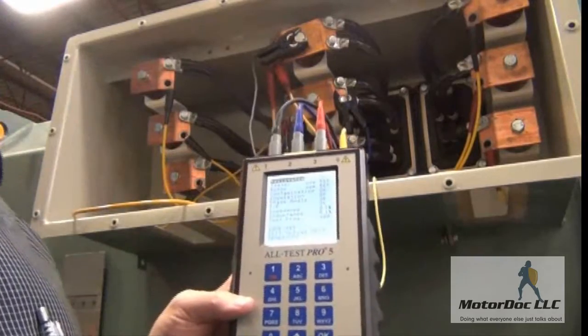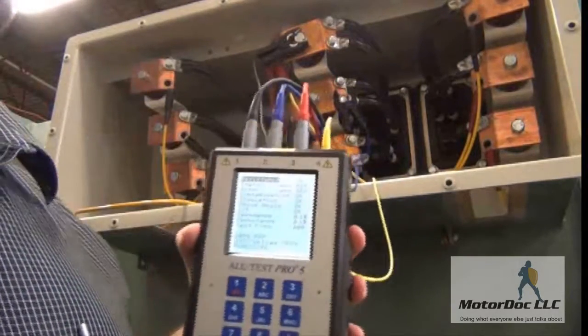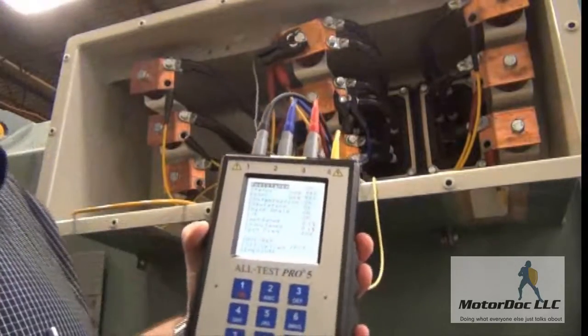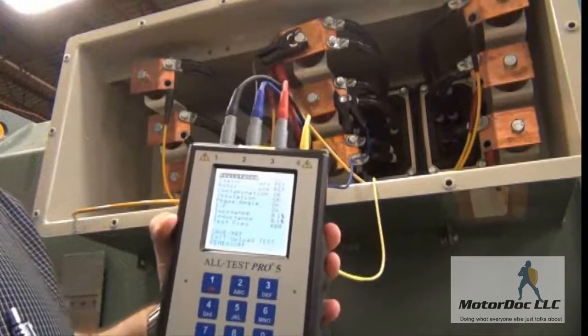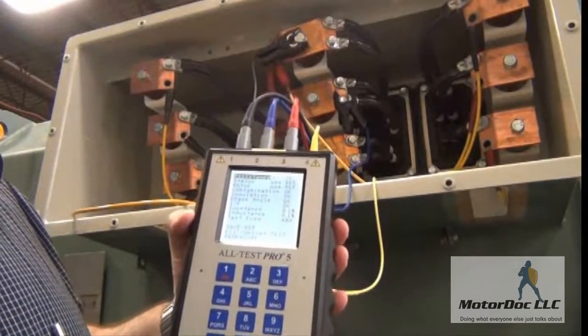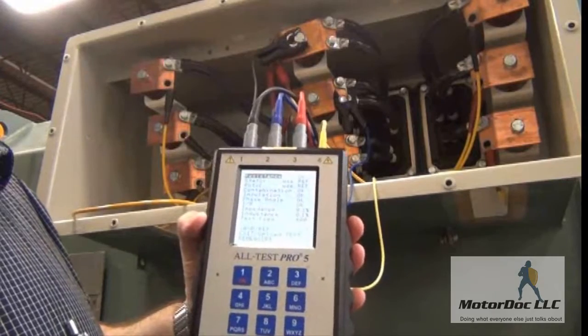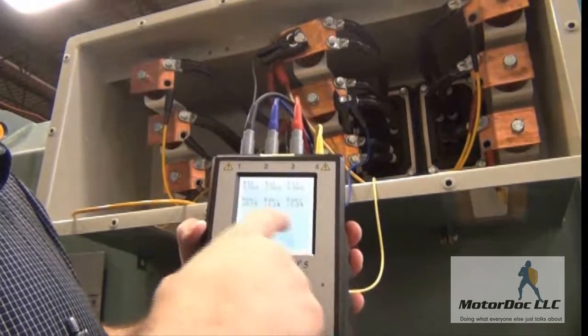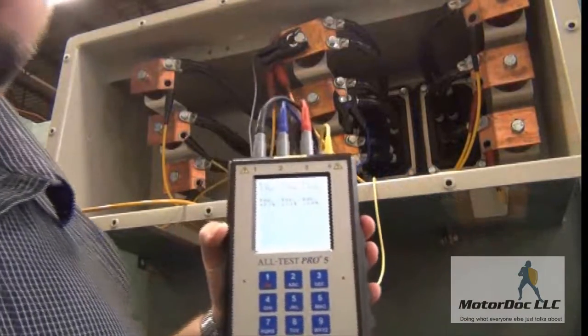This is an induction generator, so I'm expecting to see some unbalances. I'm also using jumpers, so I'll be careful with the resistance readings. It is a four-wire Kelvin unit. I highlight each test I want to look at and hit OK. The resistance readings are 2.9, 2.9, 2.8 — that's pretty good.